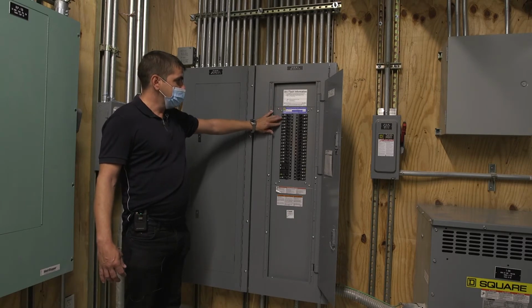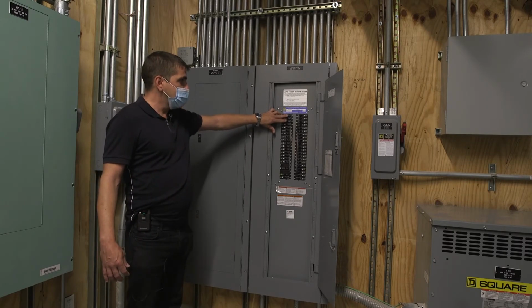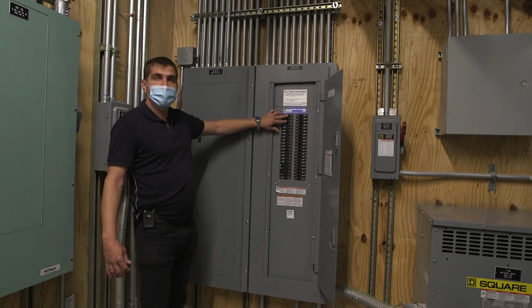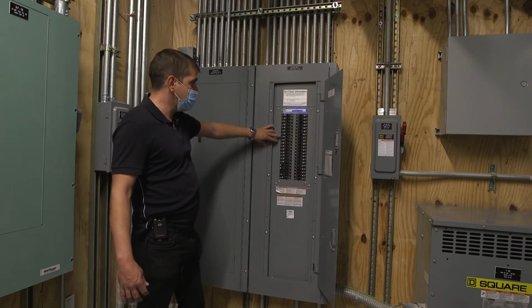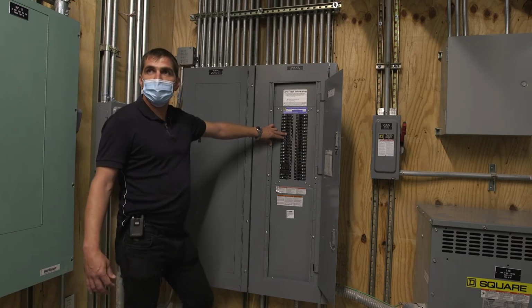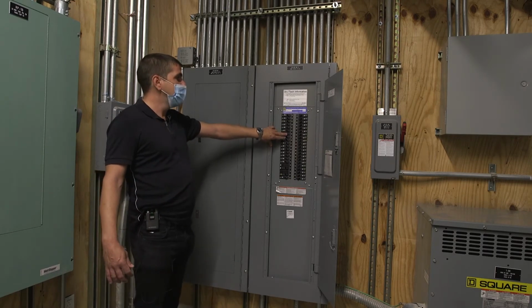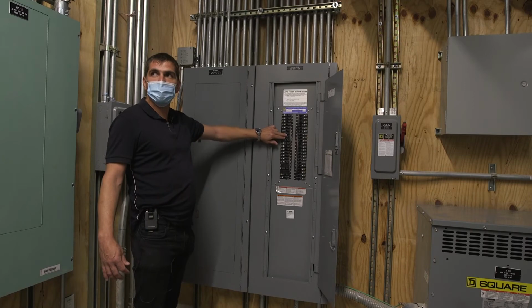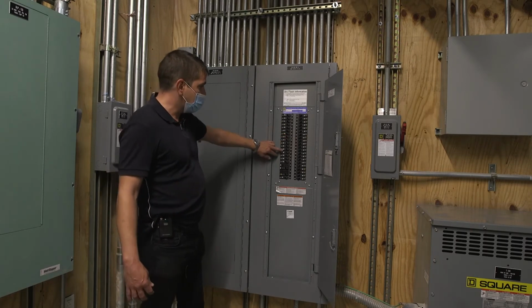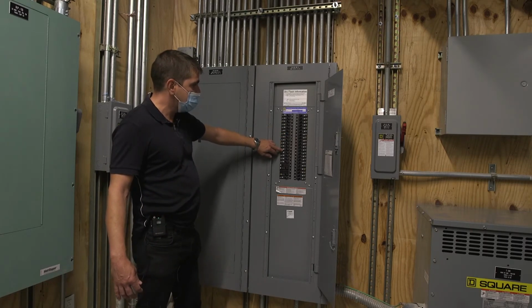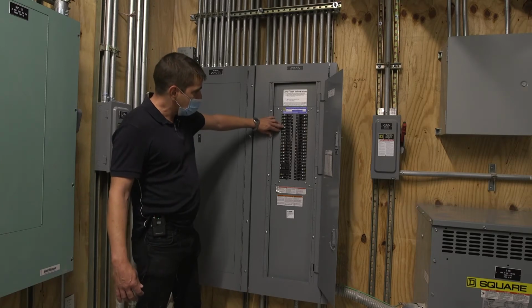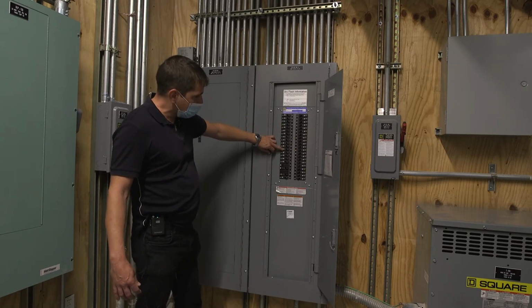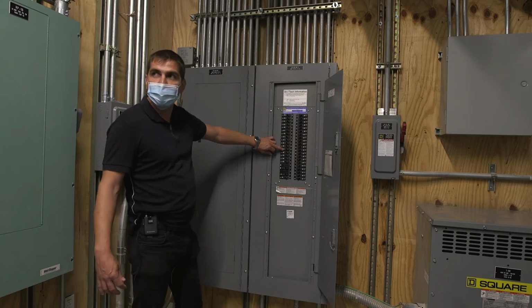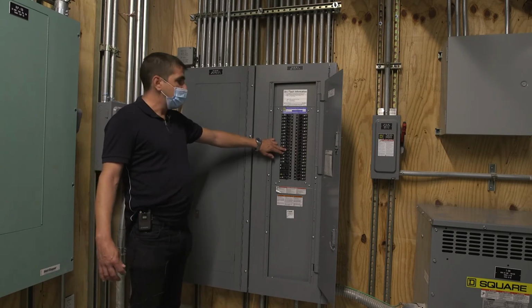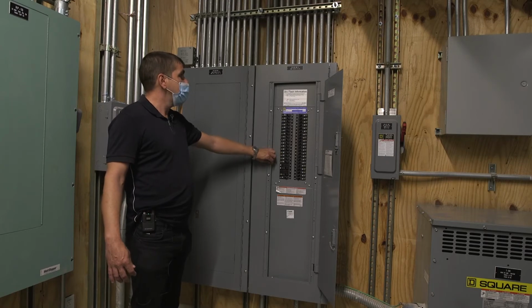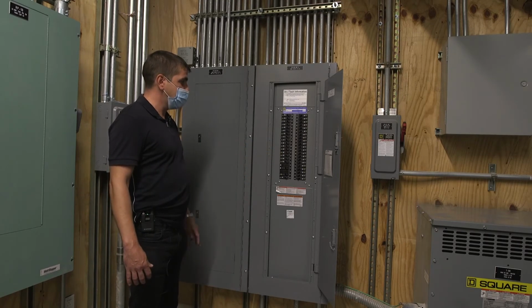All of the circuit breakers should normally be in the on position. In case there is an interruption and a circuit breaker trips, it's going to go to the middle position. In order to be reset, it has to be fully turned off and then turned on again. In addition, there is a little indicator here. When the circuit breaker is tripped, you can see visually the orange color here, which indicates the breaker is tripped. Other than that, the equipment doesn't require any specific maintenance.